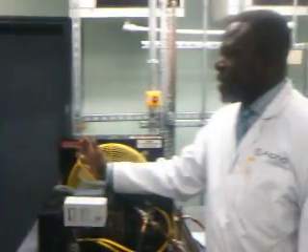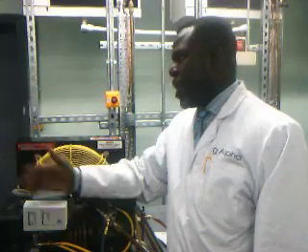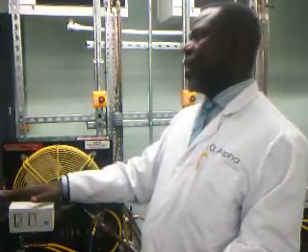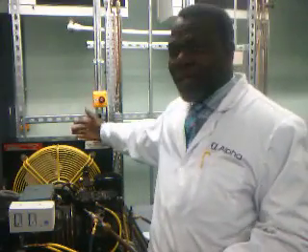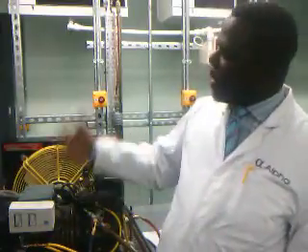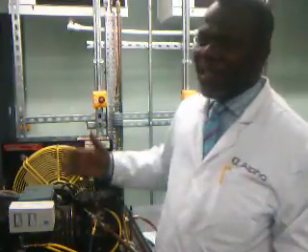Every condenser has a capacity. So when you do your heat load calculation and get your total heat load, you use that to select your condensing unit. If you select a condensing unit, it will come with the compressor, condenser, and the fan. But if you buy them separately, then there is a matching.